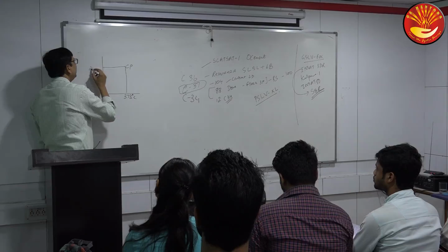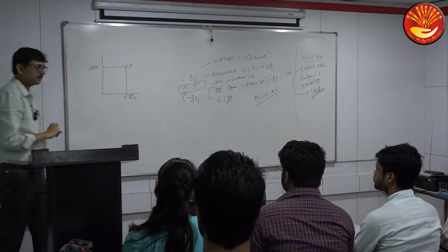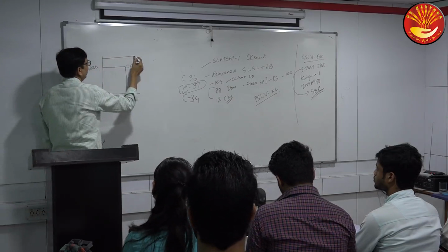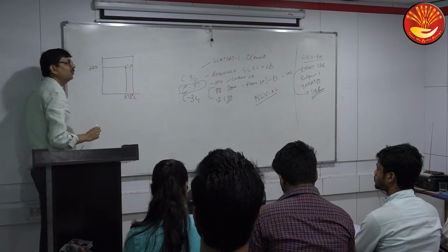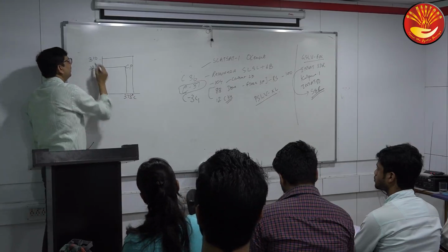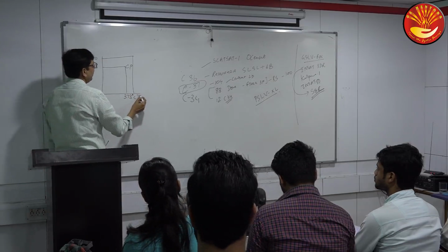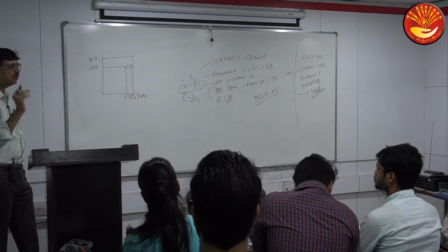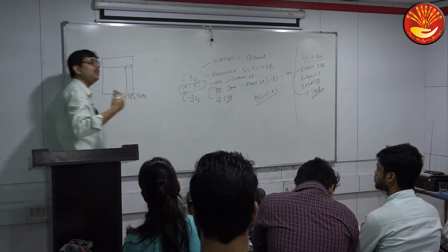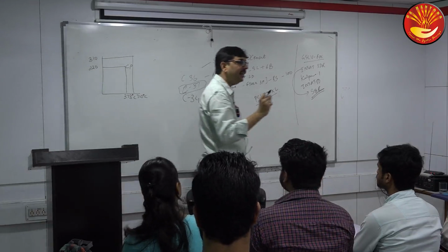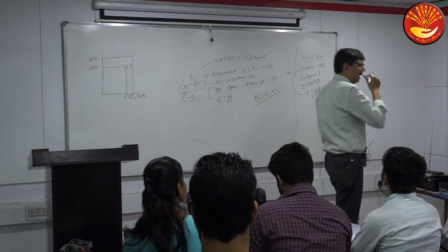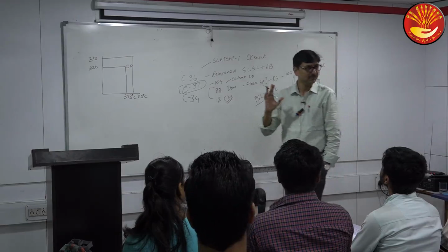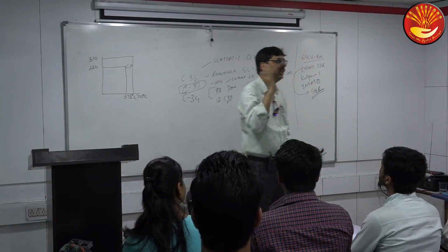Celsius and the pressure is somewhere around 220 bar. In case of an advanced ultra supercritical plant, the parameters will be 310 bar and 710 degrees Celsius. And what is the common point? The moment a thermal power plant is operating above the critical point, the efficiency is bound to be above 45%. Anything above 45% you should take.